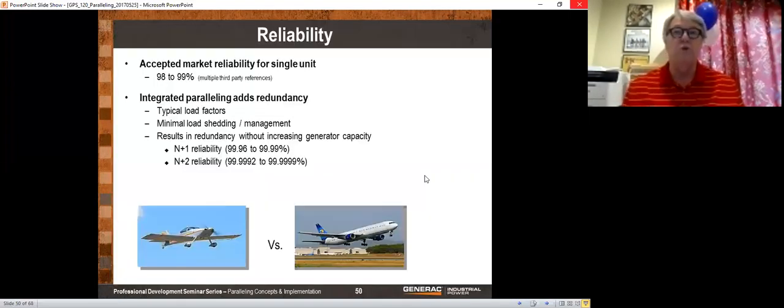So we're back to reliability. You would never put a single engine on a jet because the jet would crash, so we always have redundant engines. And there are many places in society where we use redundancies, like redundant processors on the space shuttle. Some people will say, well, I want 2 batteries in my generator because that enhances the reliability, or 2 starters. Well, why don't I have 2 generators? And the fact is that with 2 generators, in most cases 2, 3, 4, 5 generators, this may not sound logical, but it's actually less expensive.